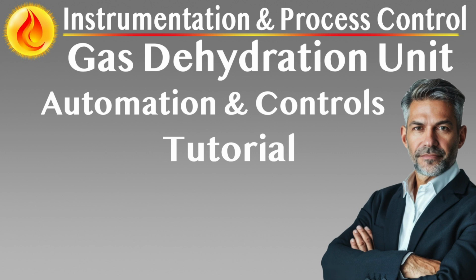Safety and protective functions. Gas blow-by protection. A high pressure switch, PSH, located upstream of the level control valve alerts against blow-by conditions due to LCV failure. Interlock logic ties into ESD to isolate the contactor and downstream equipment.